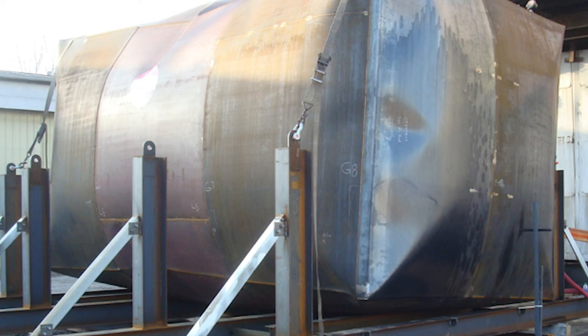But at the end, at 25 PSI, it was a rectangular tank that certainly wanted to continue its development into a round sphere until failure, in which a weld seam on the side wall had ruptured on the secondary. We had monitored the tank throughout the entire test process. The test in itself lasted nearly all day.